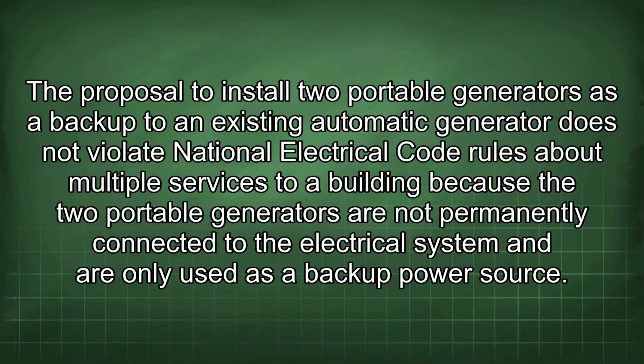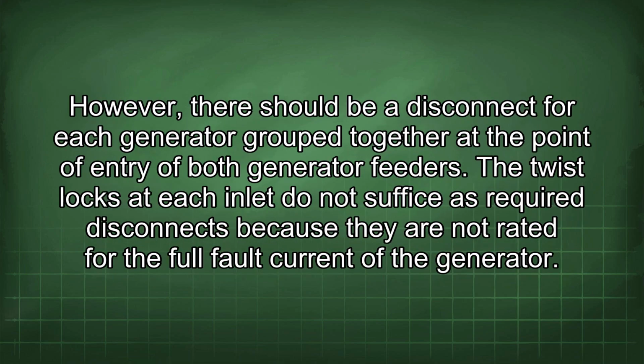The proposal to install 2 portable generators as a backup to an existing automatic generator does not violate National Electrical Code rules about multiple services to a building because the 2 portable generators are not permanently connected to the electrical system and are only used as a backup power source. However, there should be a disconnect for each generator group together at the point of entry of both generator feeders. The twist locks at each inlet do not suffice as required disconnects because they are not rated for the full fault current of the generator.